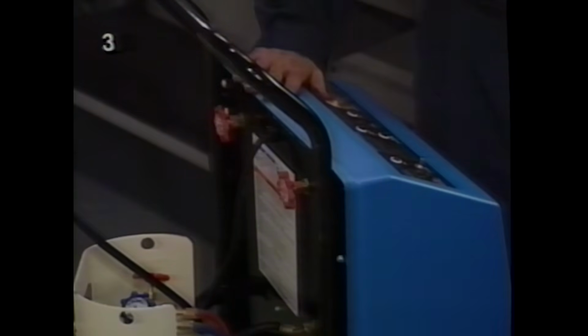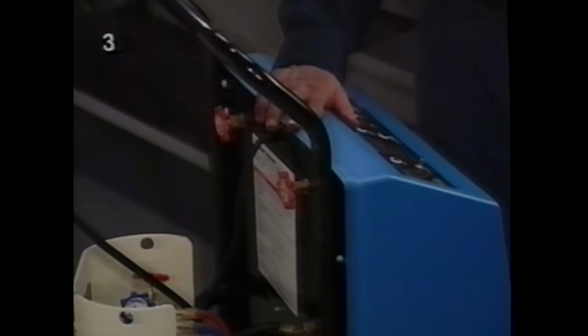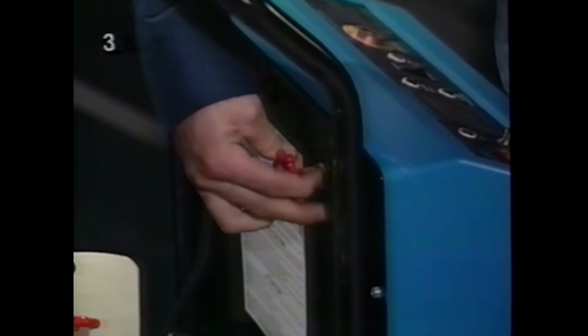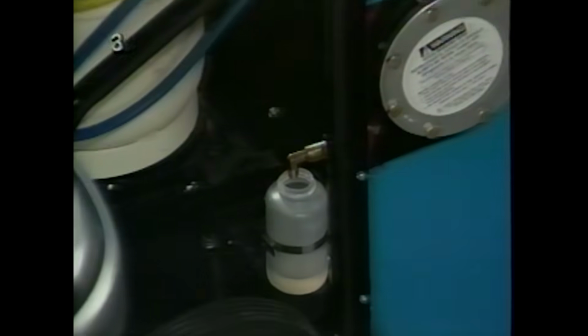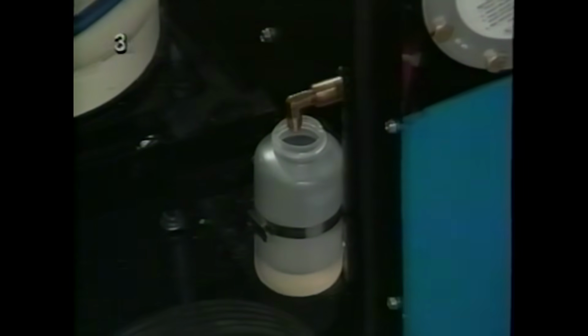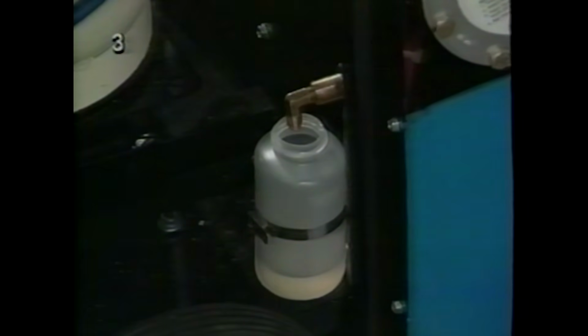Next, you want to get all the oil out of the accumulator. Open up the accumulator pressurizing valve on the ACR3 for 15 seconds. This lets some pressure back into the accumulator. Slowly open the drain valve at the bottom of the accumulator and let the oil run out into the calibrated cup. Close the valve when the oil stops running. Be sure not to let all of the pressure out of the accumulator.